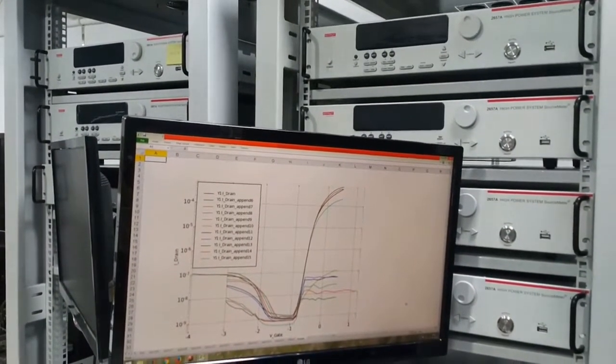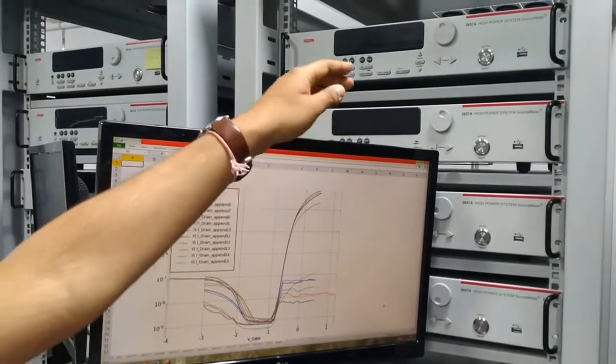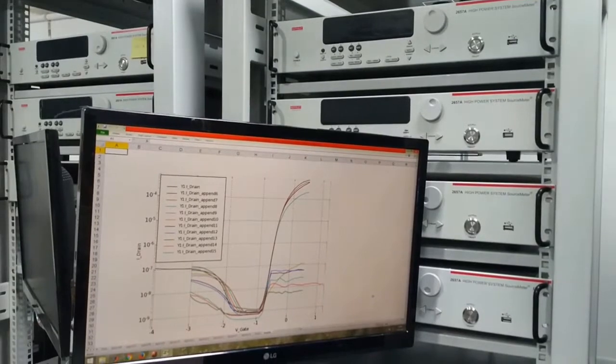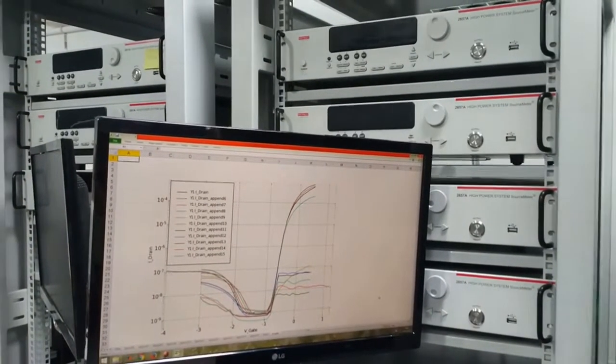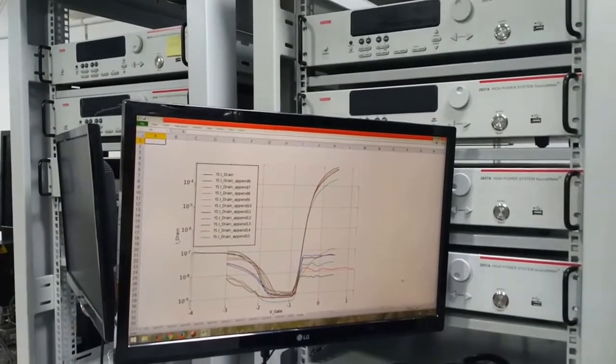For example, we can carry out measurements under moderate power regime and also high power regime. In the moderate power regime, we can go up to 200 volts on the voltage scale, and measure up to 10 amperes on the higher side and down to 0.1 femto amperes on the lower side.